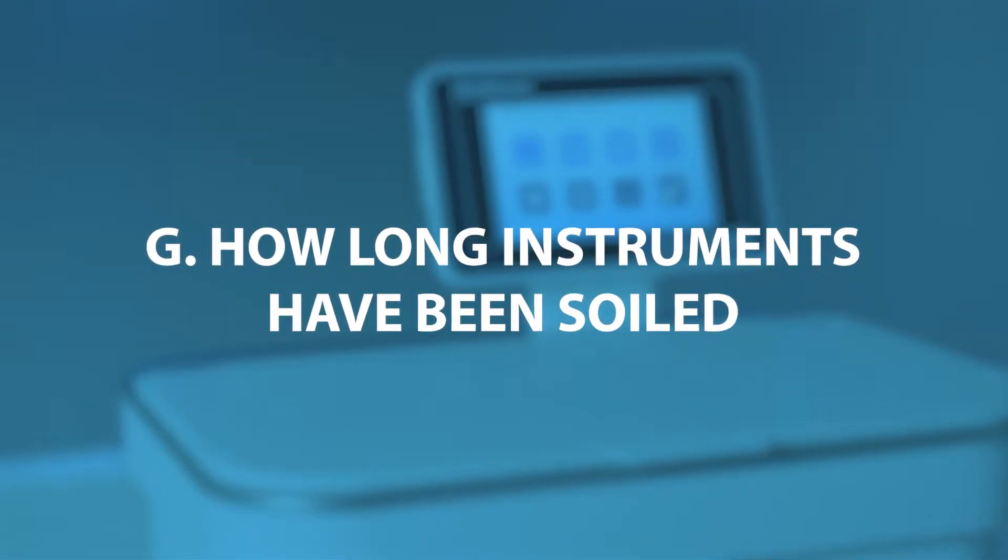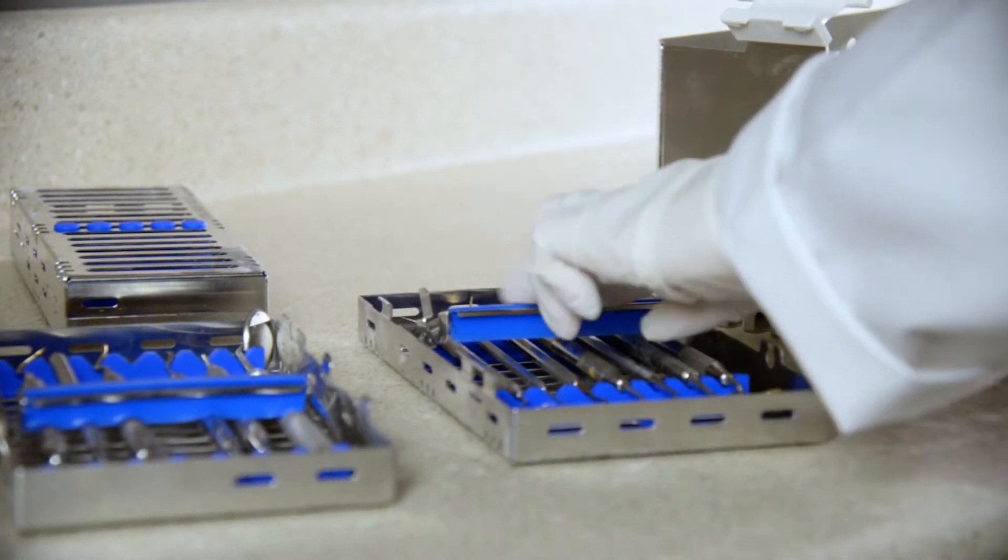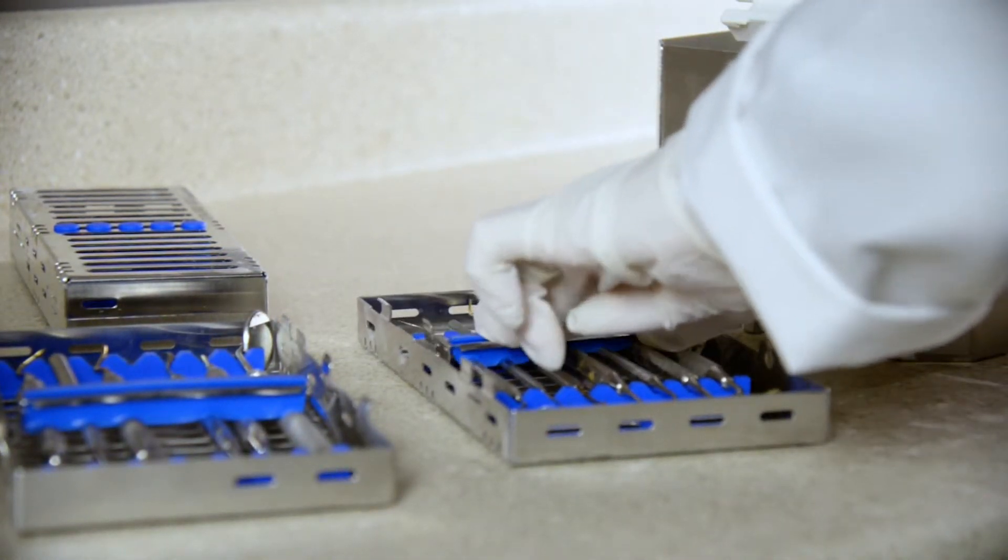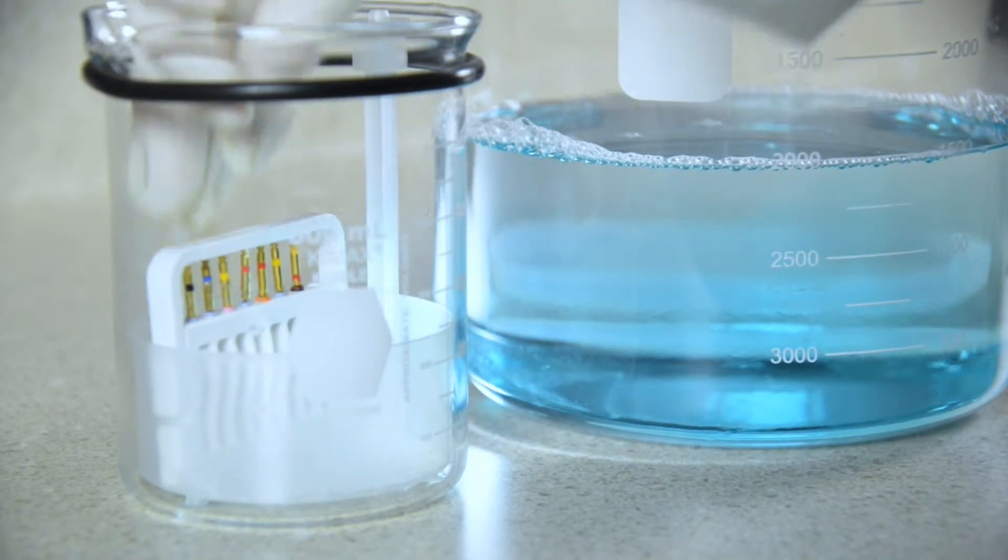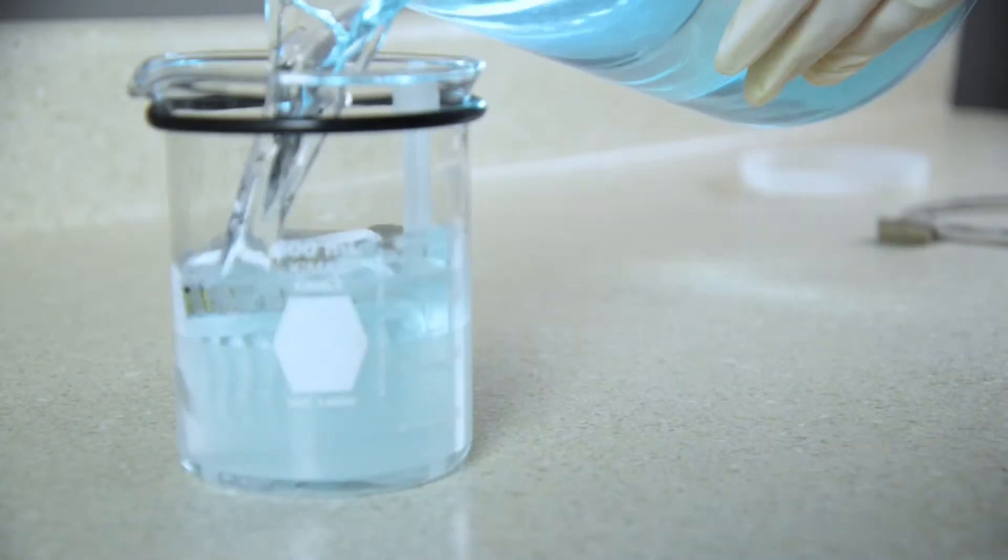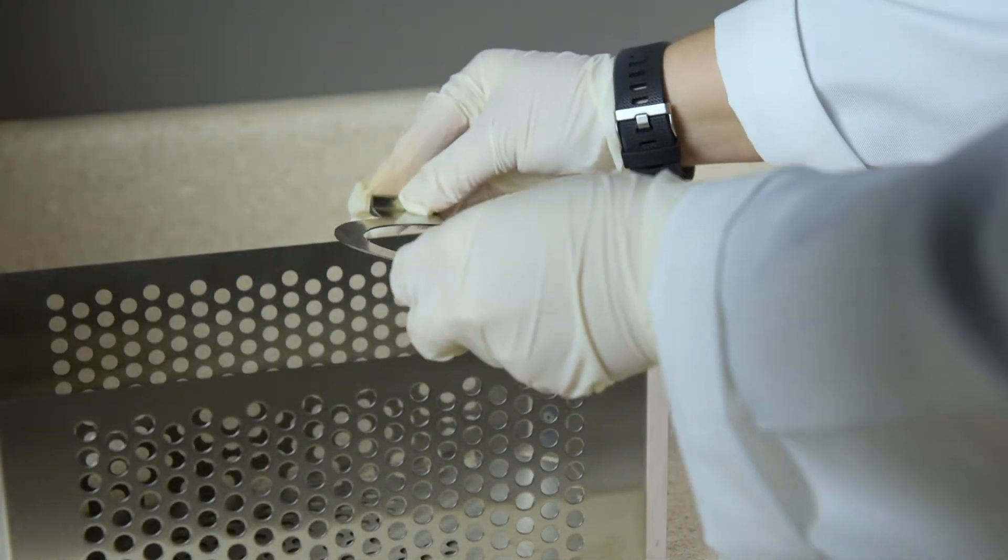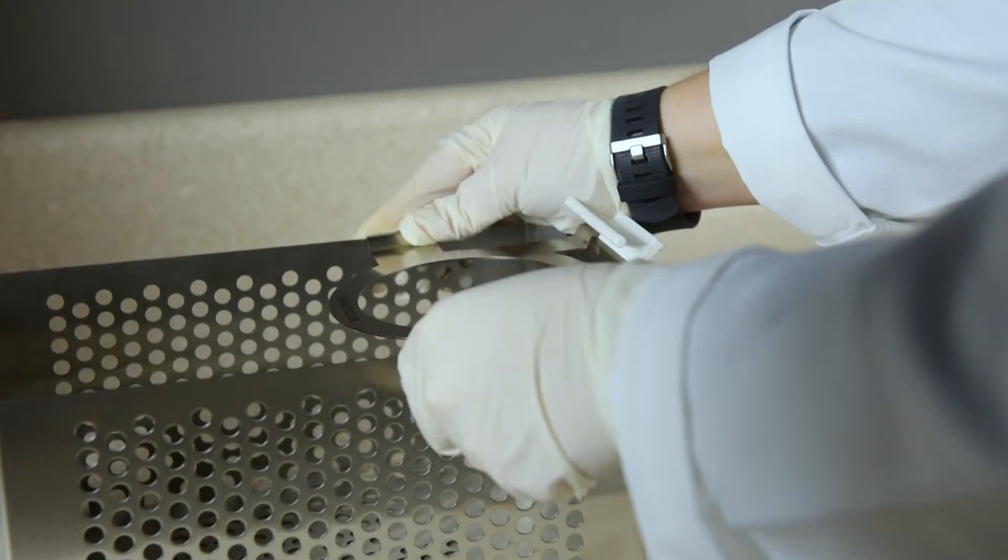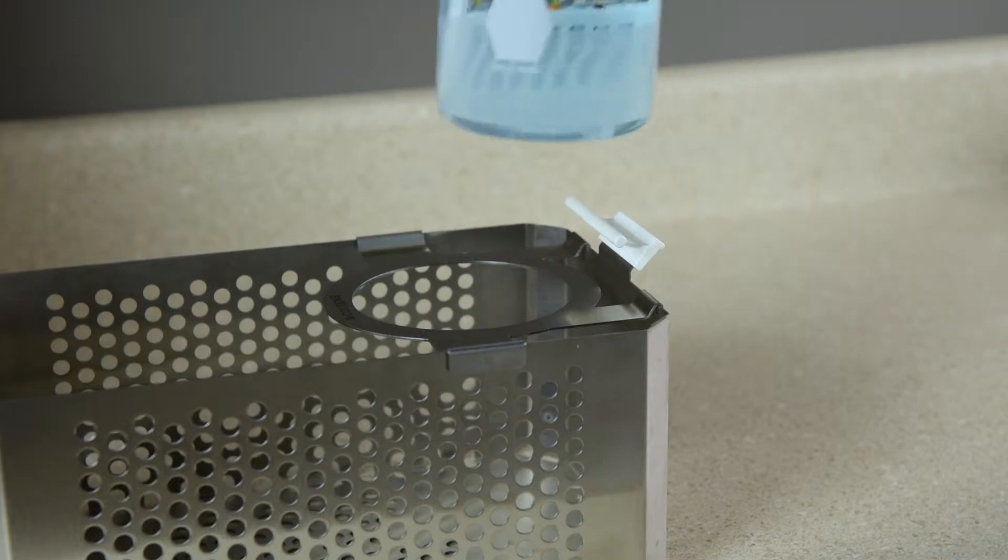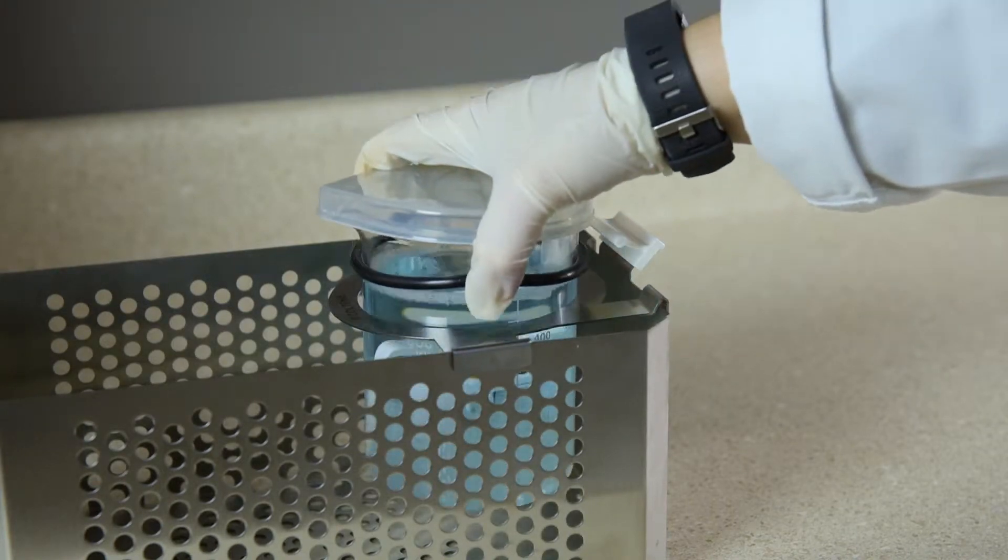How long instruments have been soiled prior to cleaning? Soil should not be allowed to dry on instruments prior to cleaning. It should be processed immediately following a procedure. If instruments cannot be cleaned immediately following a procedure, it's recommended that they be placed in a soaking solution so the soil does not harden on the instruments. This will increase the time of the cleaning cycle. The Biosonic ST16 Dental Soaking Tray is an example of a device designed for this purpose.